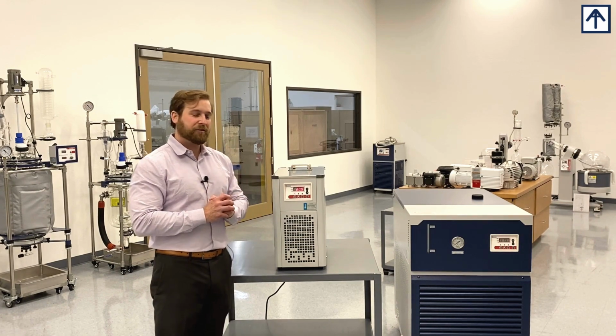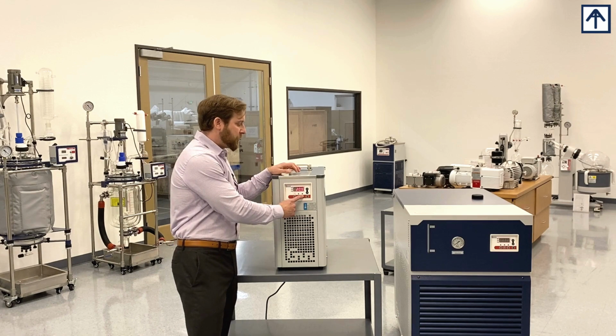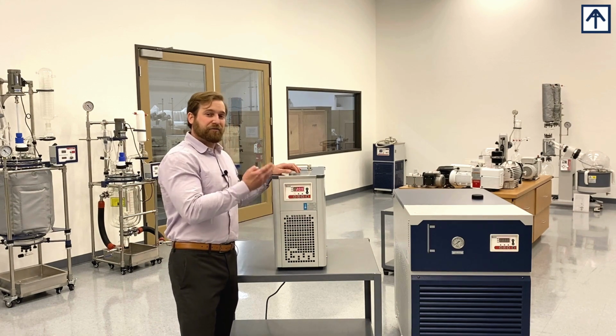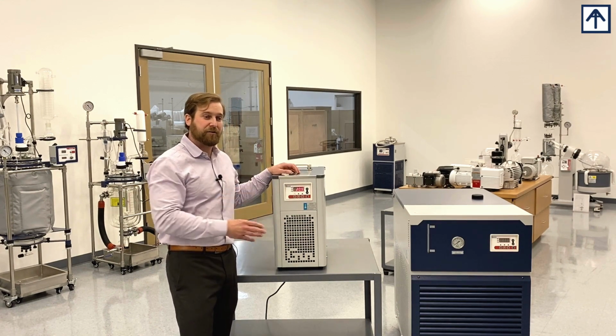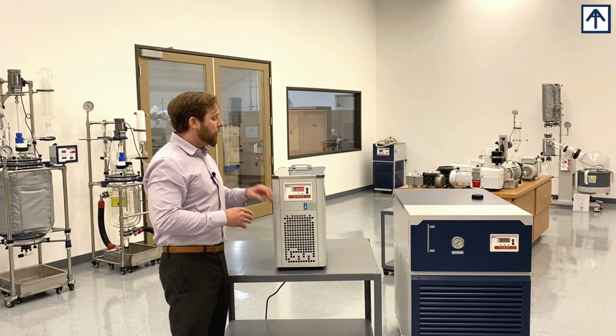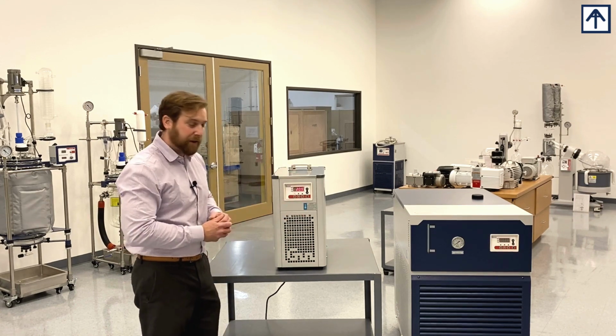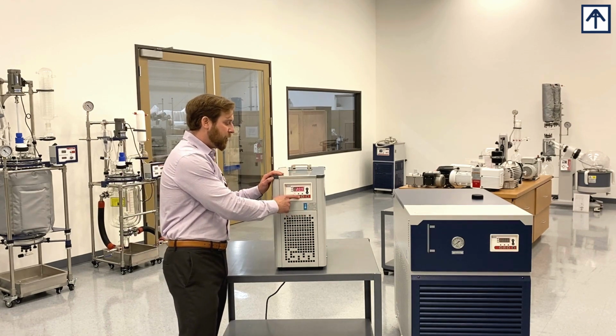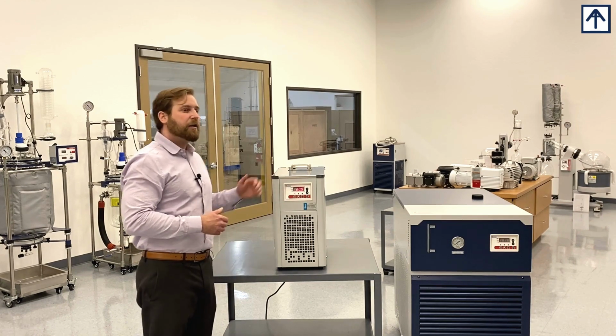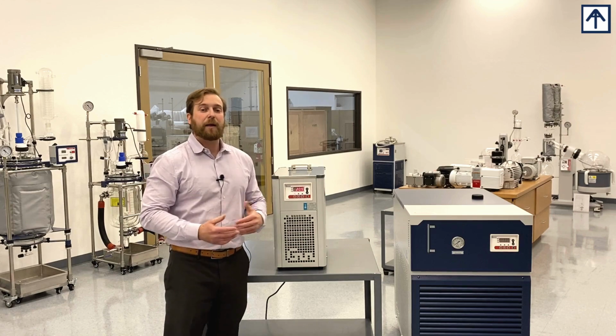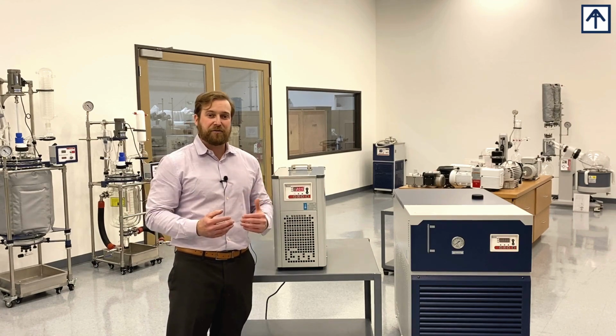The next thing we need to do is engage the circulating pump button so that the fluid is transferred to the application and back to the chiller. Once we have the circulating fluid pumping, we'll press the next button over to engage the compressor. Once engaged, the unit will be fully operational and begin to cool to its designated set point.